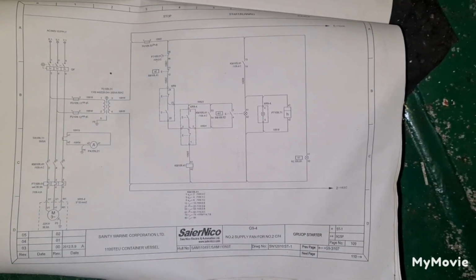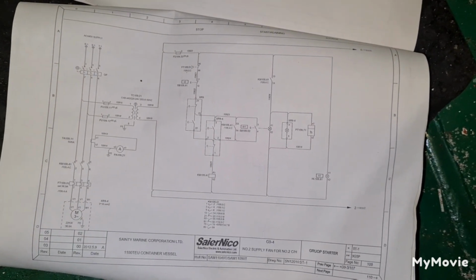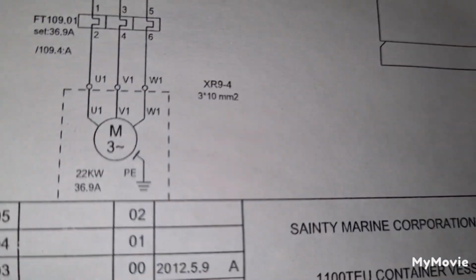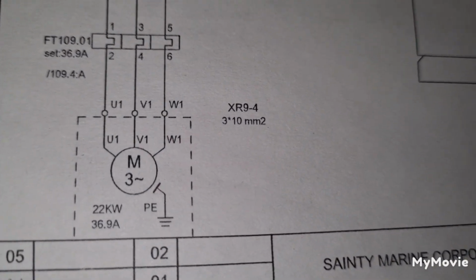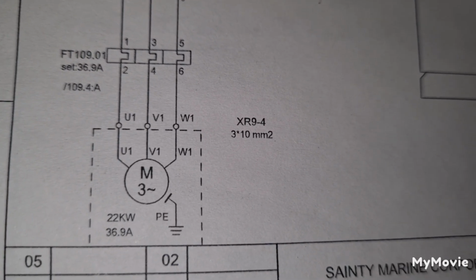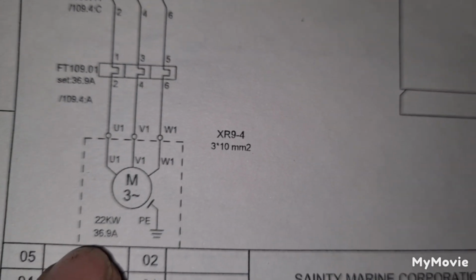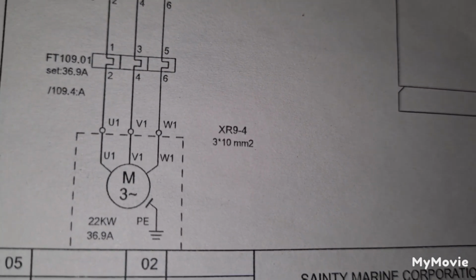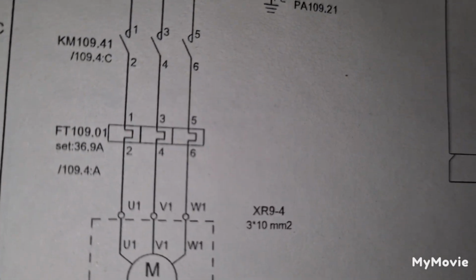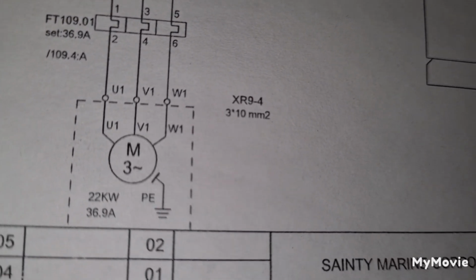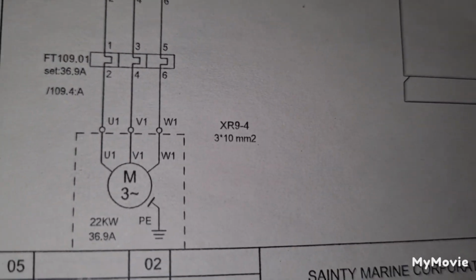So this is our wiring diagram for cargo hold ventilation fan. And as you can see, the motor is having 22 kilowatts with 36.9 ampere. So normally, when it says 36.9 ampere, you must need to set the overload relay by 36.9 ampere also. Okay, and use 3 by 10 millimeter squared.